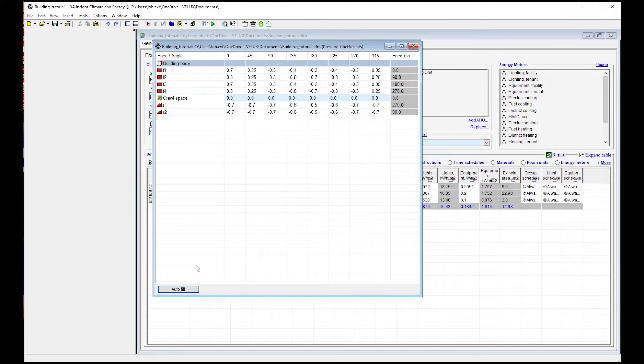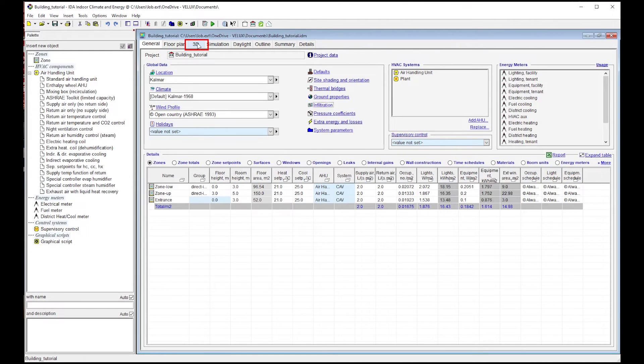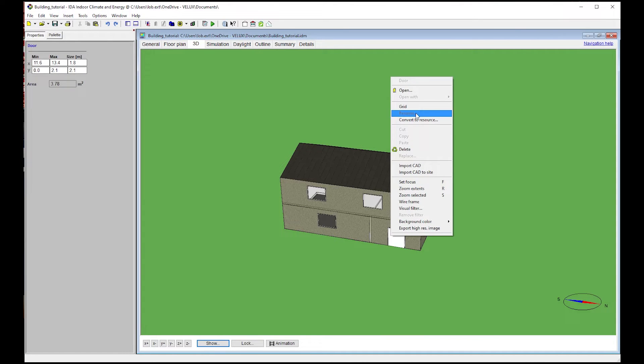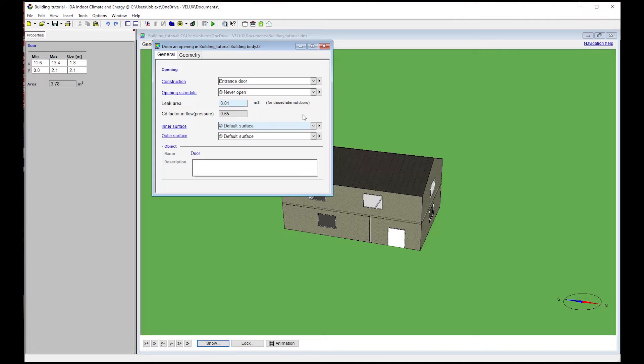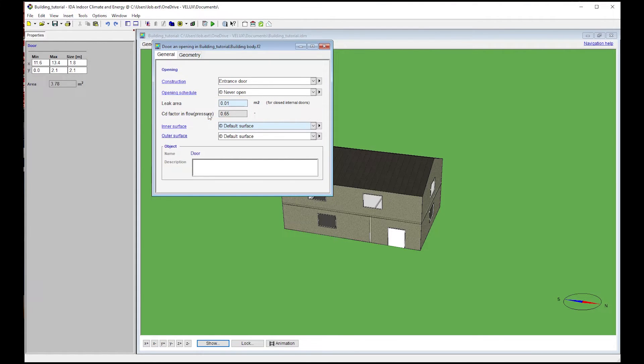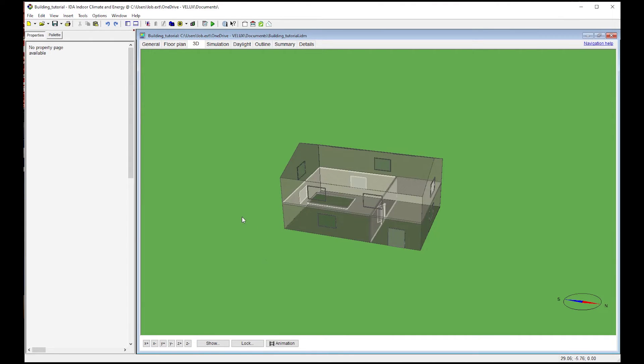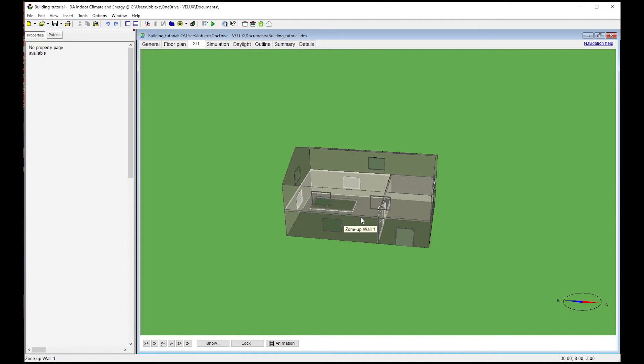Now let's look at the last input needed to simulate natural ventilation – the opening settings for windows and doors. In the 3D tab, the external door is not commonly used to circulate air, so we put 'never open' in the opening schedule. You can also define it as always open or to a set schedule. The leak area and CD factor, or discharge coefficient, are the relevant elements to simulate natural ventilation through the doors. If you don't have manufacturer data regarding the leak area, keep the default values. The CD factor depends on the geometry of the openings, but the default value will be fine. To allow the stack effect and airflow movements between zones, we modelled the staircase as a large horizontal opening without a door.